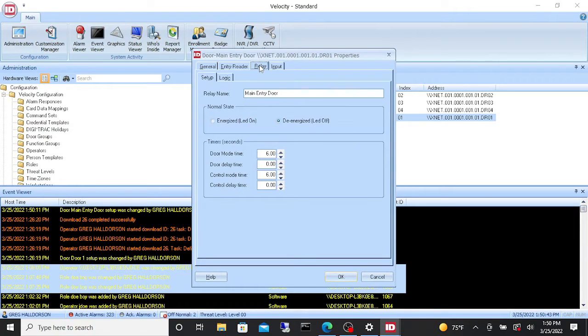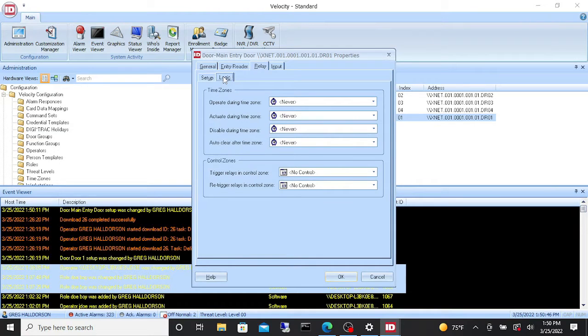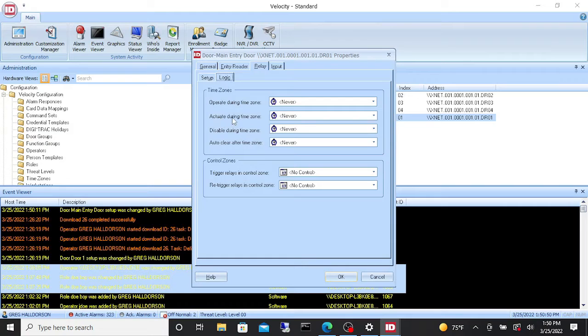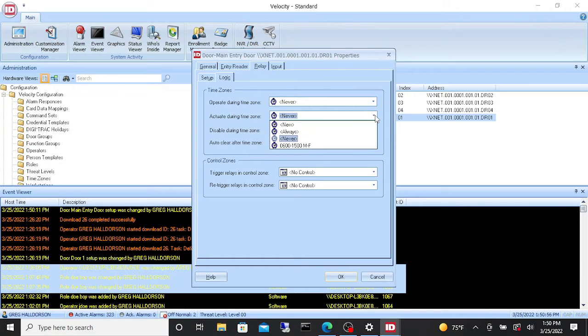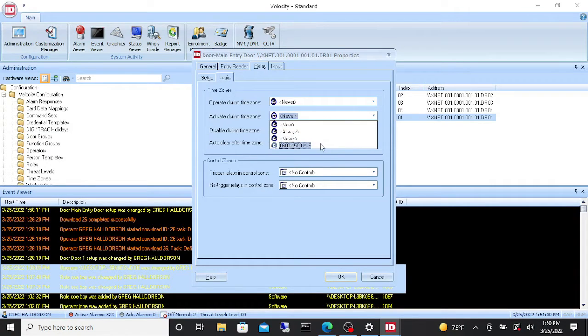We're going to go to relay and then we're going to go to logic. In here we want to set it so that it actuates during a time zone. Currently it's set up for never. If we click the drop down menu, it gives us a choice of all the time zones that we currently have built in our system.